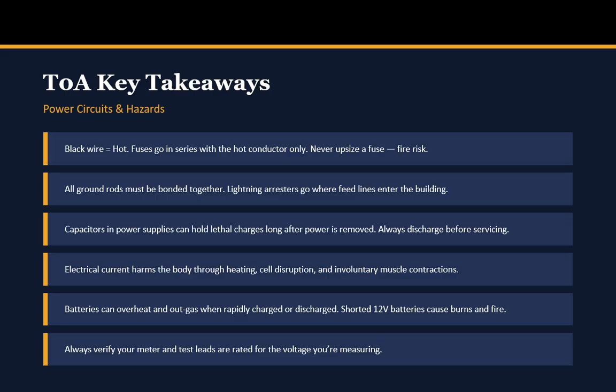Key takeaways. Black wire equals hot. Fuses go in series with the hot conductor only, and never upsize a fuse due to fire risk. All ground rods must be bonded together. Lightning arresters go where the feed lines enter the building. Capacitors in power supplies can hold lethal charges long after power is removed.